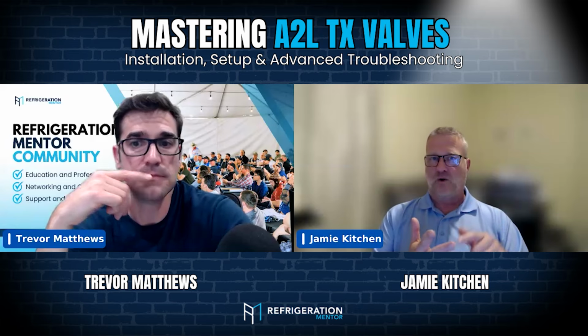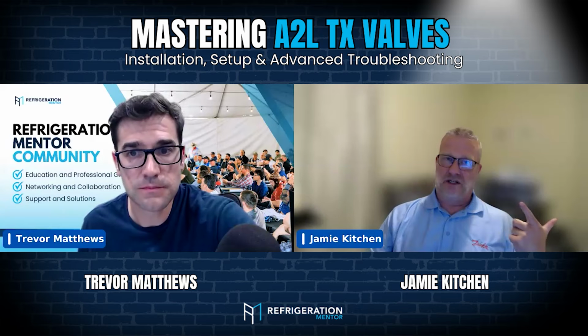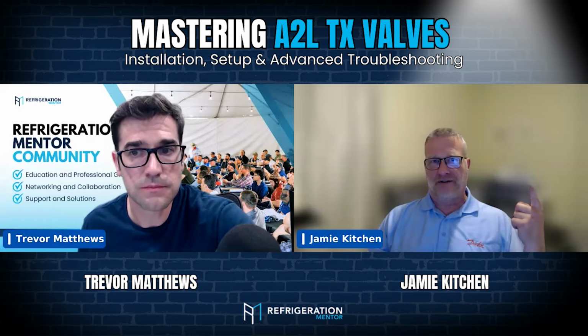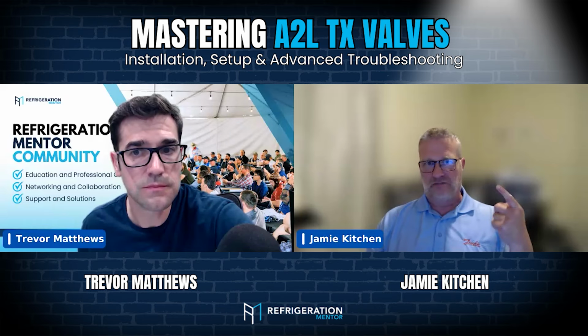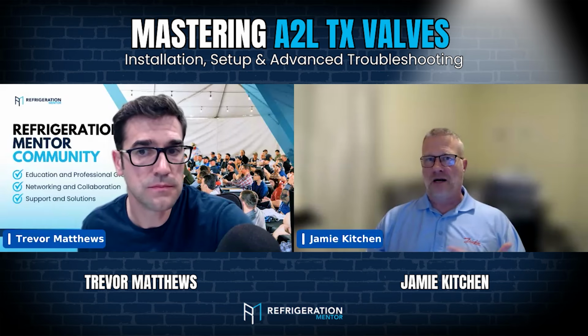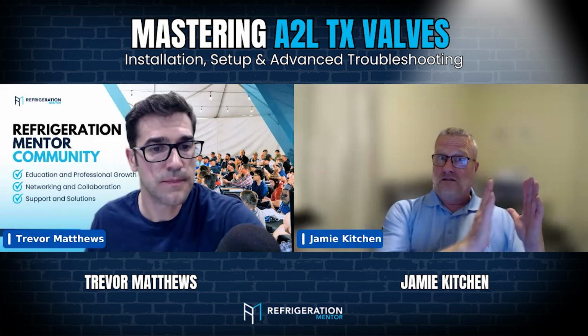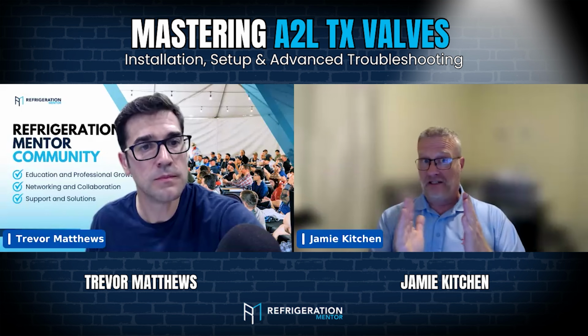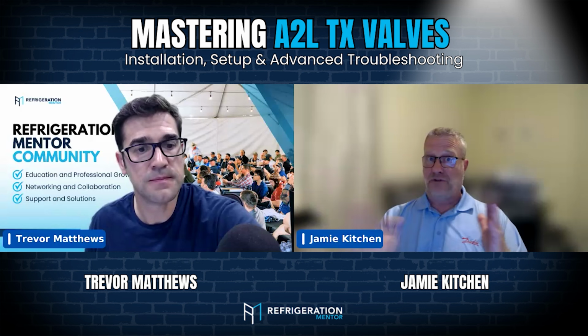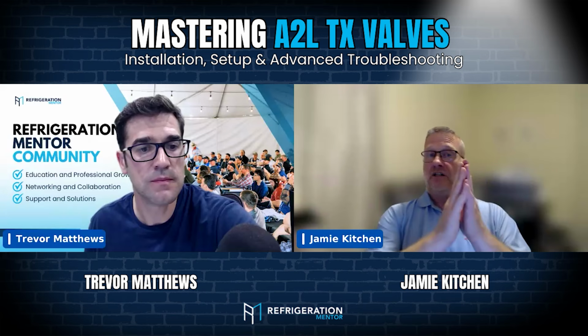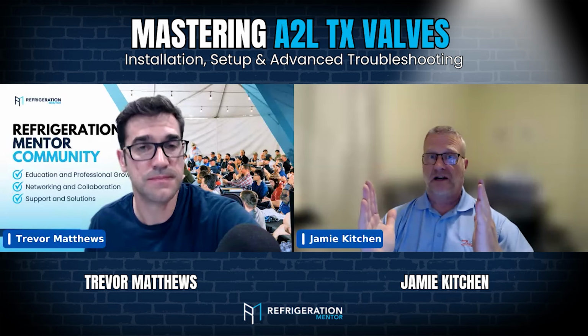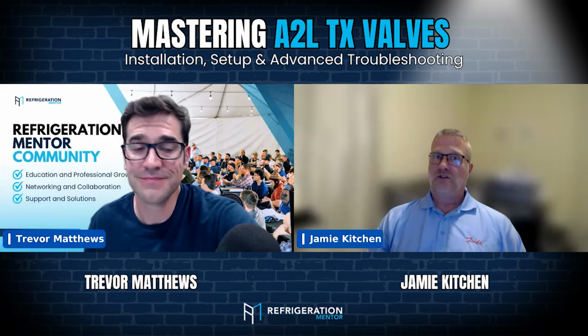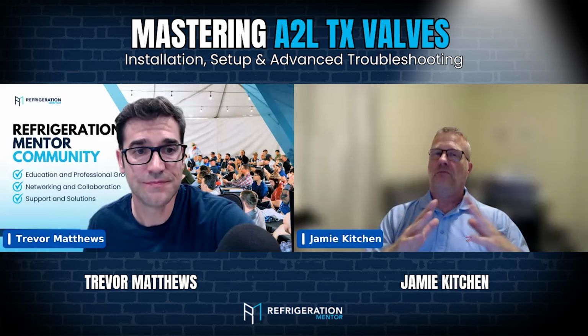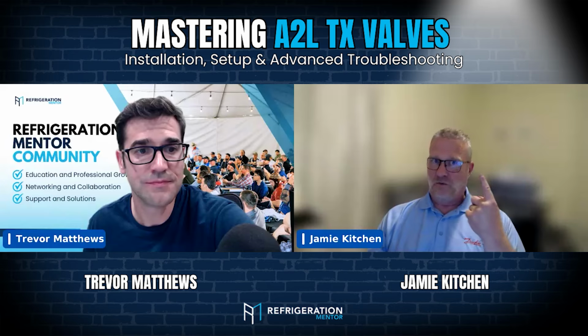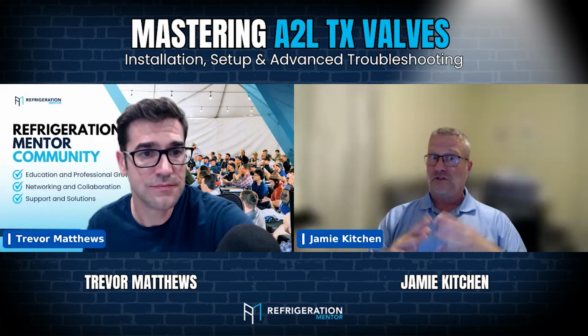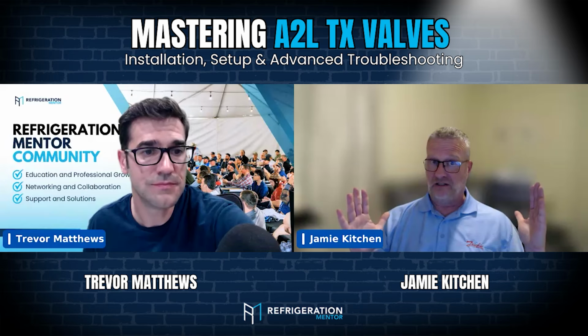It comes with Chatleff and Aeroquip flare connections, and it comes with the waxing tape that's good for pulling the hair off your arm. It's supposed to be used for the sensing bulb installation, and it comes with the bulb strap. All you have to do is pick your refrigerant and your system capacity, and it's set up so that it's 1.5 to 3, 3.5 to 4 or 5. You pick your range of capacities on the side of the box, your refrigerant, and you're good to go. So it replaces multiple OEM valves with one, two, or three codes. You can service any air conditioning system you see out there, right?